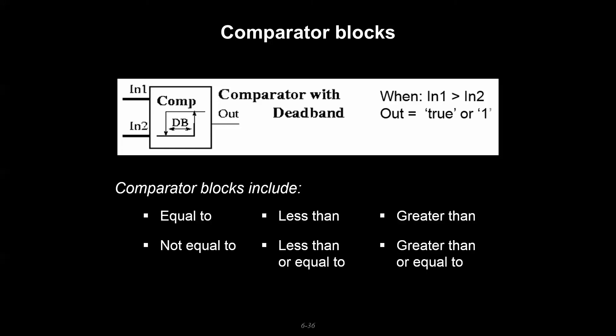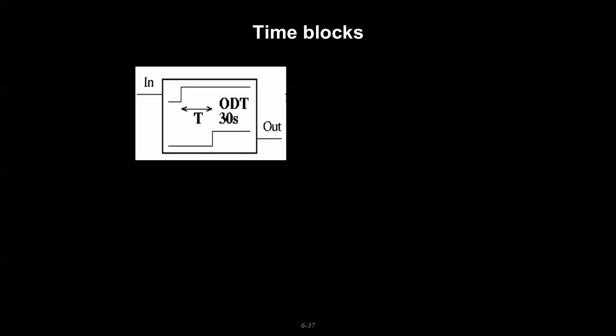Time blocks can be used in a couple different applications. You may see minimum on or off time associated with some equipment so it's not cycling. You may have some timer to help with some lead/lag or equipment rotation. There might be a start/stop delay so you can let a pump run a little bit longer once some equipment turns off to get rid of some of the load, or you could have a schedule running some of this equipment.